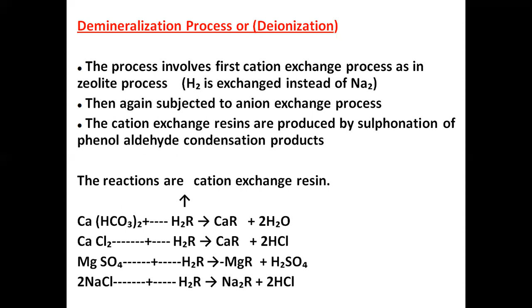These are some of the reactions involved in the cation exchange resin, which is used for the removal of hardness of water. These are the four reactions in which the calcium and magnesium are exchanged with the H plus ions present in the cation exchange resin. The water coming out of the cation exchange process will contain dilute hydrochloric acid, sulfuric acid, and carbonic acid, which can be removed by passing through the anion exchange bed.